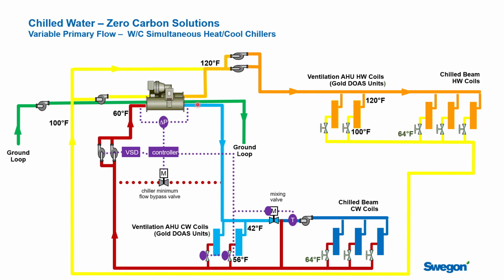If we have a surplus of heat, we would dump it into the green line. It could go into a ground loop. We have marked that here. We could store that energy in the ground during the summer, and then when we get around to the winter where we don't have enough heat in the chilled loop to meet the heating load, what we would do is take that heat, whatever we needed from this loop, and if we needed more, we would grab it from the ground loop to provide enough energy for this space.